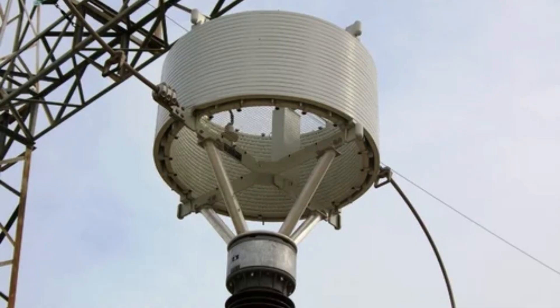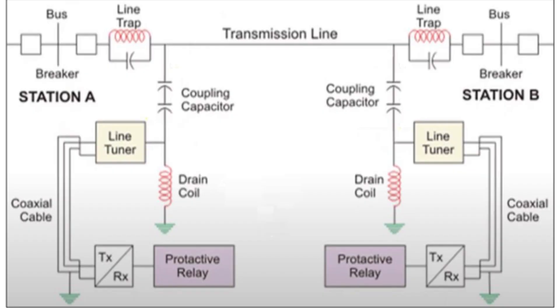The Wave Trap is placed after the Capacitive Voltage Transformer and is essentially a choke coil. It prevents high-frequency carrier signals from entering the substation by offering high impedance to those signals, while still allowing the 50 Hz power frequency to pass. This ensures that the communication signals stay on the transmission line where they belong.